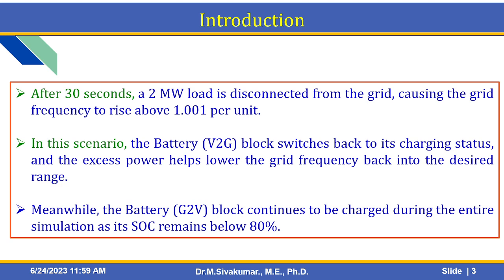After 30 seconds, a 2 MW load is disconnected from the grid, causing the grid frequency to rise above 1.001 per unit. In this scenario, the V2G battery block switches back to its charging status and the excess power helps lower the grid frequency back to the desired range. Meanwhile, the G2V block — grid to vehicle — continuously charges during the entire simulation as its state of charge remains below 80%.